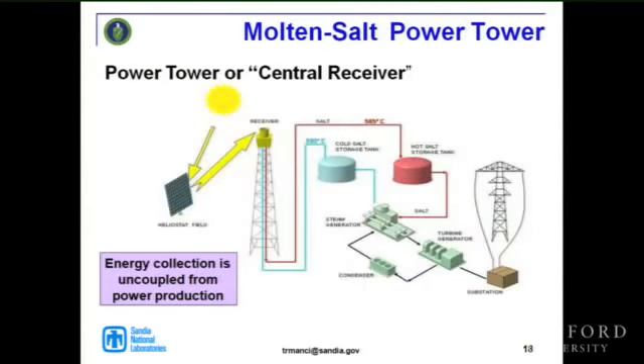It also demonstrated an external efficiency of 88%. The way it operated was that you had a cold tank of salt, which is always in the liquid phase. You heat it up initially to melt it, around 220 C, maybe heating it to 250 C and putting it in the cold tank. Then when you want to collect solar energy, you pump it through the receiver and heat it up to 565 C, putting it in the hot tank.